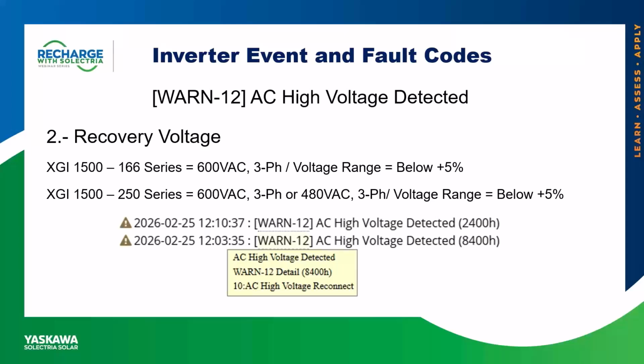So for a 600 volt AC inverter, that would mean that your voltage when the unit is waking up in the morning, or if it faulted out, has to be below 630 volts AC. For a 480 volt AC unit, the voltage needs to be below 505 volts AC. And what's going to happen is if in the morning the voltage is higher than that 5%, the unit is trying to grid connect, but since the value is higher than the recovery voltage settings, it's going to fault out with Warn 12 AC high voltage detected.